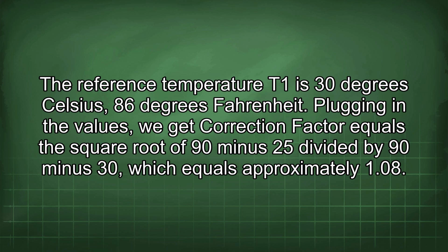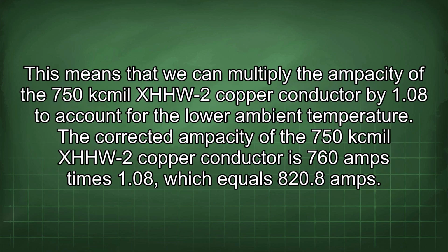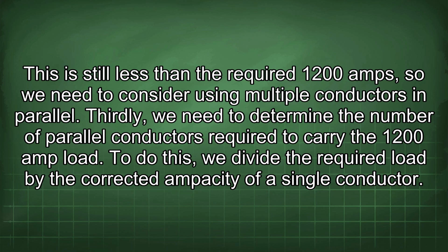Plugging in the values, we get correction factor equals the square root of (90 minus 25) divided by (90 minus 30), which equals approximately 1.08. This means that we can multiply the ampacity of the 750 kcmil XHHW-2 copper conductor by 1.08 to account for the lower ambient temperature. The corrected ampacity of the 750 kcmil XHHW-2 copper conductor is 760 amps times 1.08, which equals 820.8 amps. This is still less than the required 1200 amps, so we need to consider using multiple conductors in parallel.